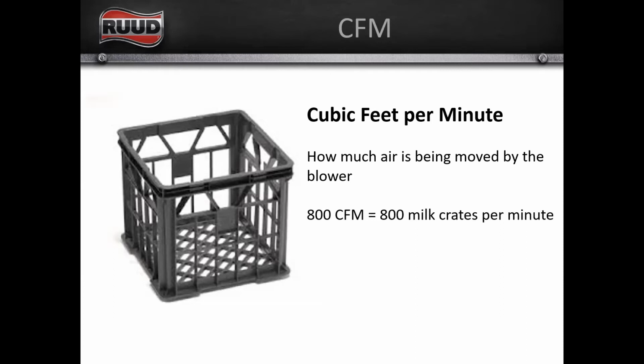And when we think about, say, 800 CFM, I think about 800 milk crates of air per minute, right? 800 cubic feet per minute of air moving through the ductwork. And when I look at ductwork, or start measuring static pressure, if we've got a rated amount of air in cubic feet per minute that we've got to move through some ductwork, the more restrictive that ductwork is, the harder it is to move the air through it, quite simply, right? So a lot of times it's not just about how the equipment is configured, but about how the ductwork is laid out, and that can be as challenging as anything else, especially if we're doing retrofits or change outs, right?